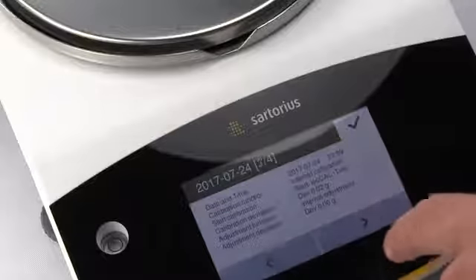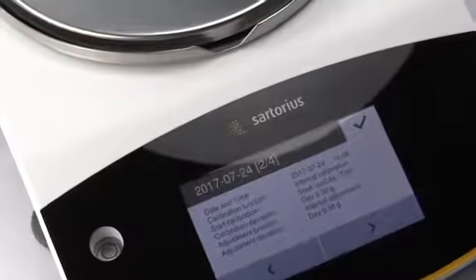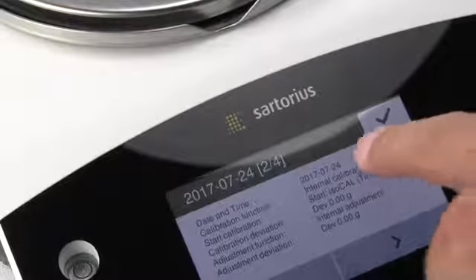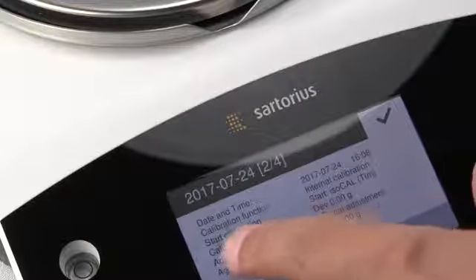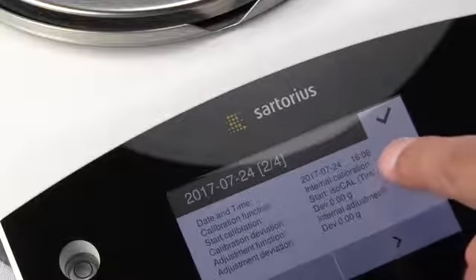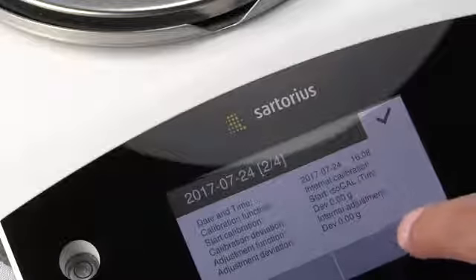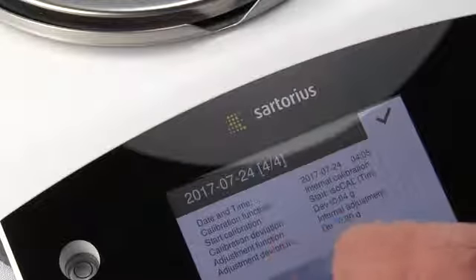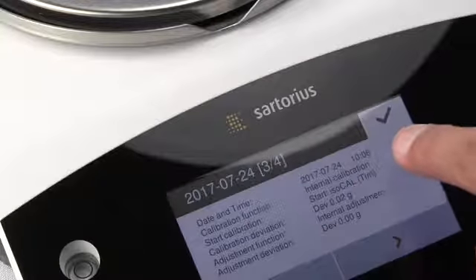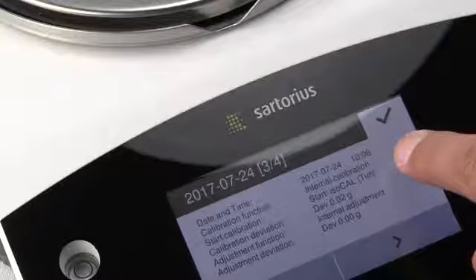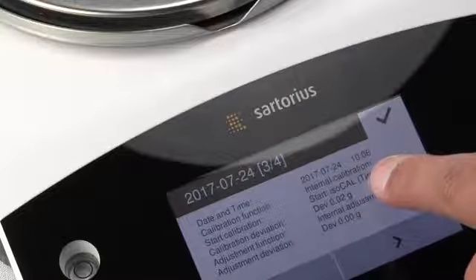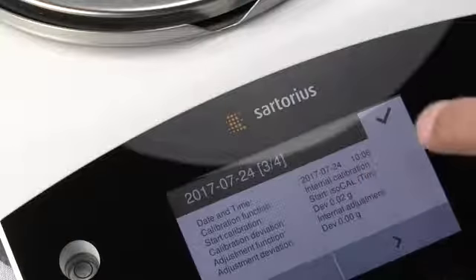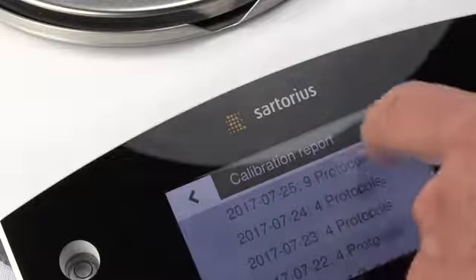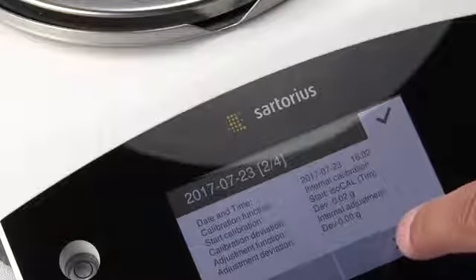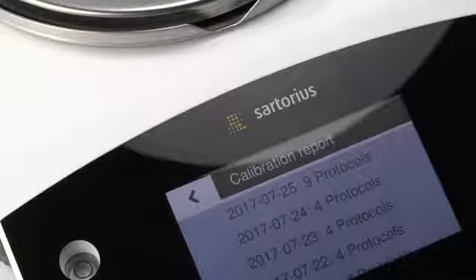So you can see the other time the balance was calibrated, July 24th, and here, if you notice, so now we have internal calibration, but it tells us this time that the calibration was started because it was ISOCal, and the standard deviation again was 0. And so here's one. You can see, again, it was ISOCal, and now the calibration deviation was 0.02, and so it documents everything for you. And you can see, we can just scroll through, and there's lots of cal reports there.